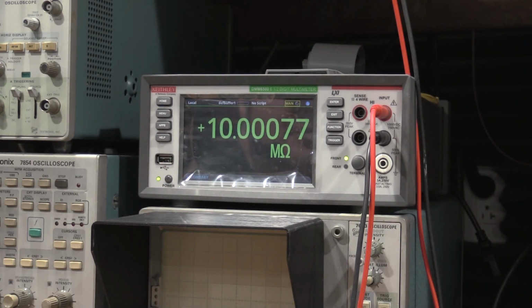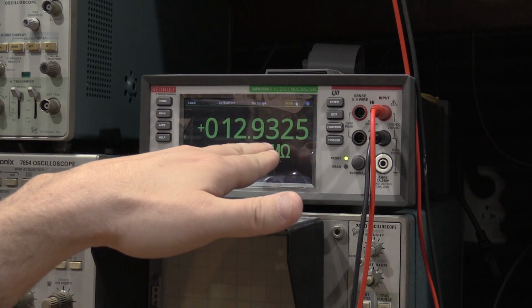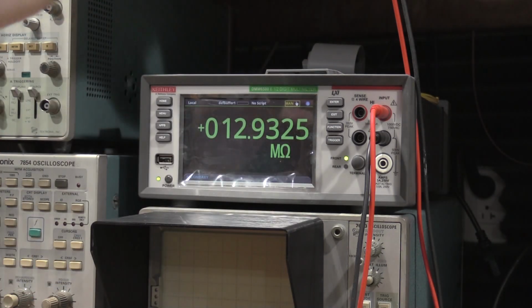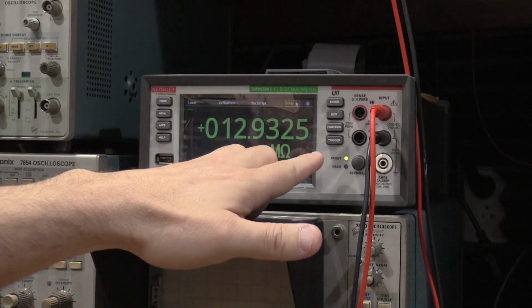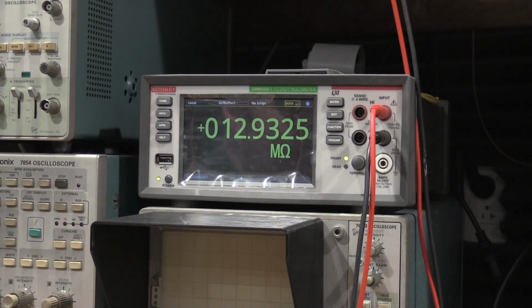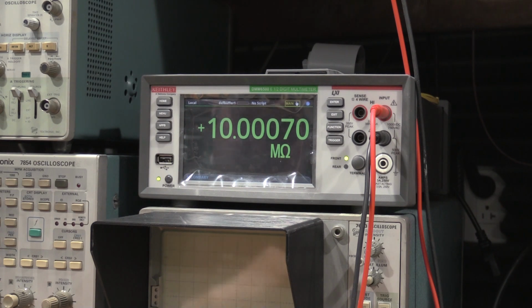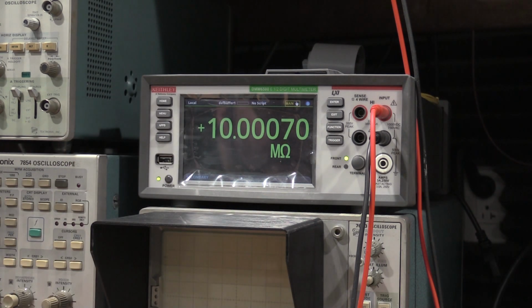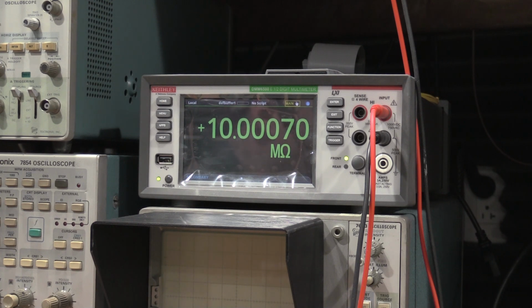even the 8840 has a high input impedance. 12-ish, 9 megohms. If I go to the 200 volt range on the 8840, this is why I've been using this meter specifically. It is the closest I have to 10 megohms in the lab. That's the only reason. So anything that's close to 10 megohms is good, but I did this same measurement with the 7510 when I had it, and the 8840 at 200 volts gives me 10.000 megohms, so I can't ask for better.